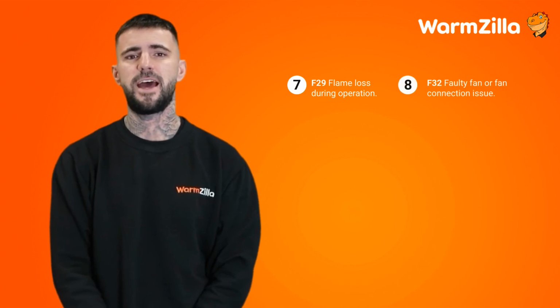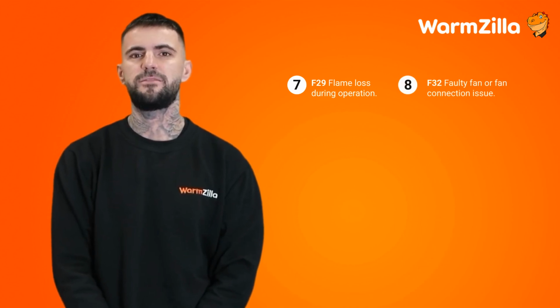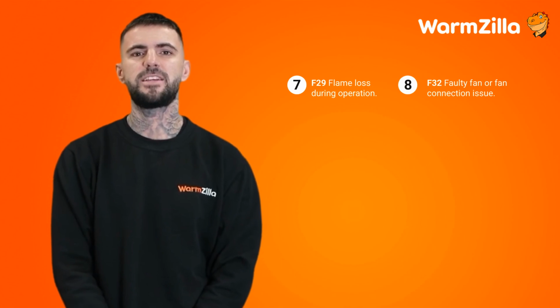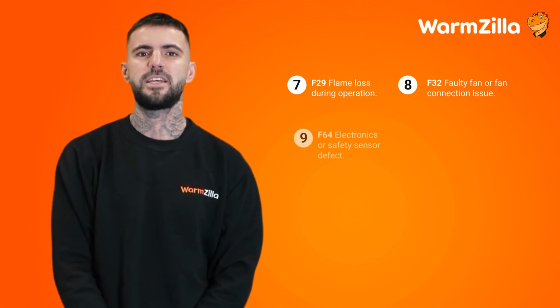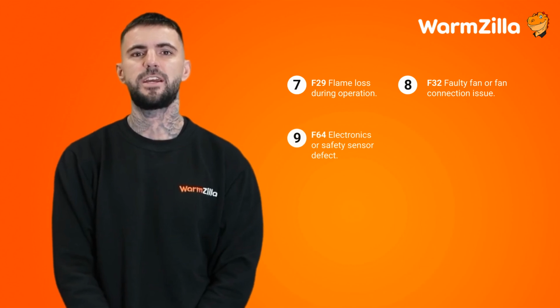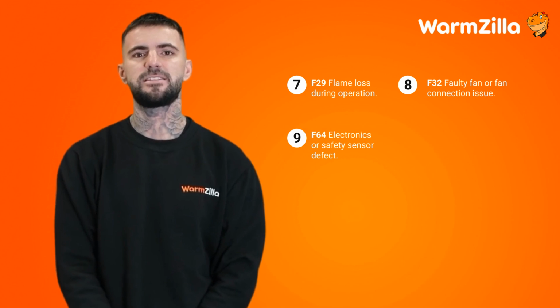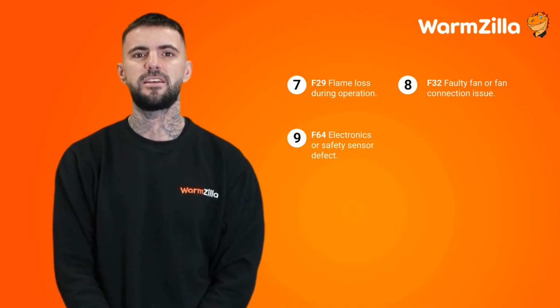F32 is a faulty fan or fan connection issue. Check the fan wiring, connections, and replace the fan if necessary. F64 shows there is an electronics or safety sensor defect. Simply inspect the PCB and sensors and replace the faulty components.